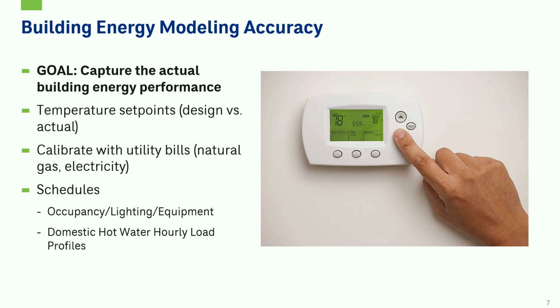So then it's also important to reflect on how the building is actually performing and what heating and cooling loads will be required from your ground heat exchanger throughout the year. Our goal is to capture that actual energy performance versus what we might think it is performing. So we want to ask the question of how spaces are actually maintained. We know that the design point with the codes is sometimes 72 degrees cooling and 70 degrees heating for an occupied residential space.